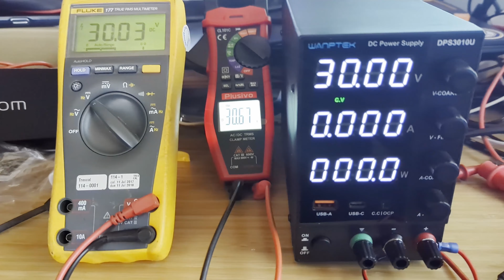We'll do 10 just as an example here. So you're approximately 2% off right here, which is within the spec when you're looking at voltage. And here you go at 20 volts, we're reading 20.4, where the Fluke is reading 20.01. We'll go up to 30. And as you see here, it's off by more than a half a volt. It's about 0.7 volts difference. That's pretty large. I found that the amperage readings were also wildly inaccurate, and I have a short clip here that will show that.